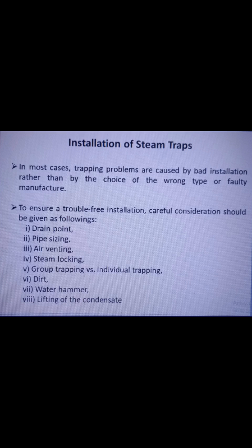Third one is air venting. When air is pumped into the trap space by the steam, the trap function ceases unless adequate provision is made for removing air, either by way of the steam trap or a separate air vent. The plant may take a long time in warming up and may never give its full output.